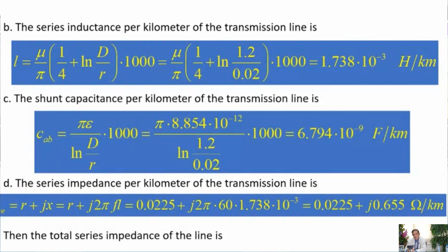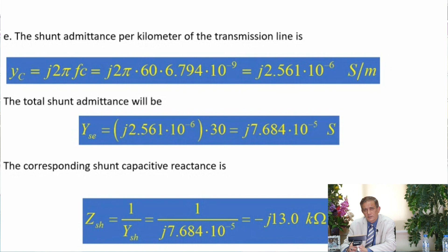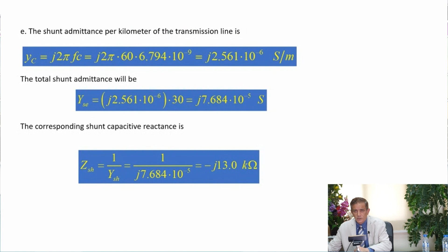Shunt admittance, YC: we use admittance for the capacitor because capacitor impedance is 1 over omega C, so admittance is omega multiplied by C, given in Siemens per meter. For the total shunt over 30 kilometers, we multiply by 30. This gives Y, and 1 over Y is the impedance, which is the total shunt impedance of the transmission line. Is there anything not clear in this example?